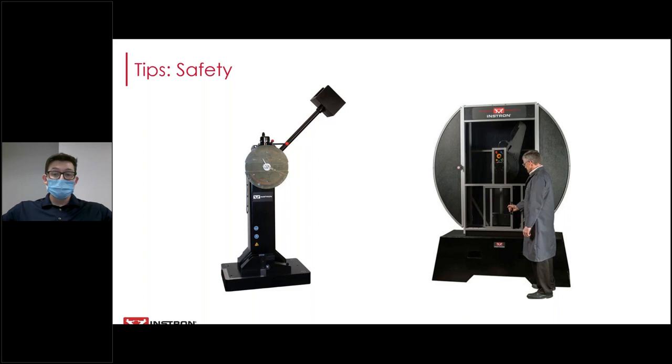can be something as simple as ergonomics. If you have a frame bolted to the floor, like a lot of the manual ones on the left here are, your test is colliding with your specimen around your ankle height. So in order to reinsert new specimens, you have to bend over frequently, depending on how many tests you're doing, and this can certainly cause strain to your operator over time.